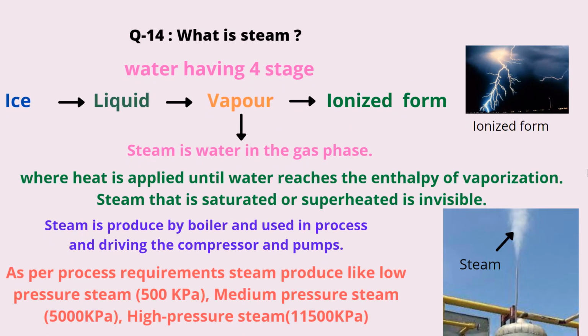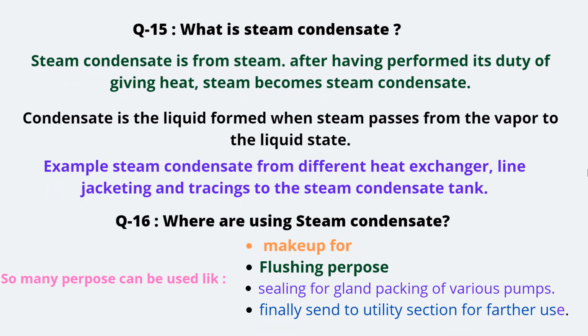What is steam? Water has 4 stages: ice, liquid, vapor, ionized form. Steam is water in the gas phase, where heat is applied until water reaches the enthalpy of vaporization. Steam that is saturated or superheated is invisible. Steam is produced by a boiler and used in the process and for driving compressors and pumps. As per process requirements, steam is produced as low pressure steam at 500 kPa, medium pressure steam at 5000 kPa, and high pressure steam at 11500 kPa.